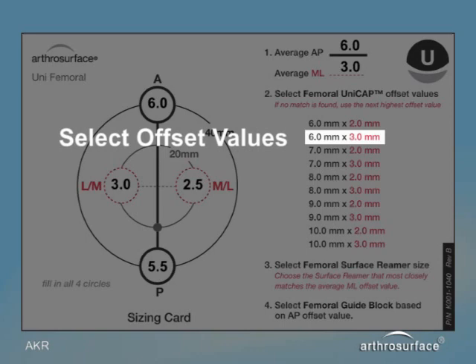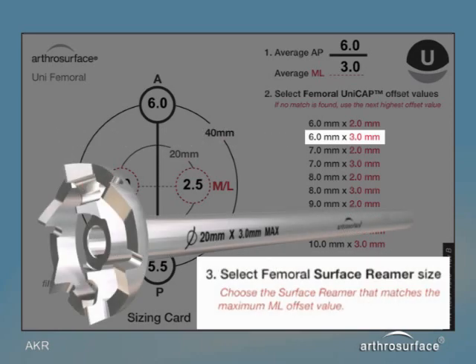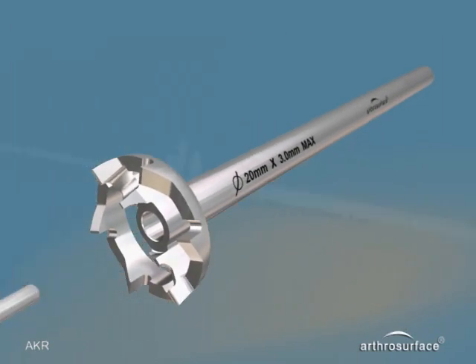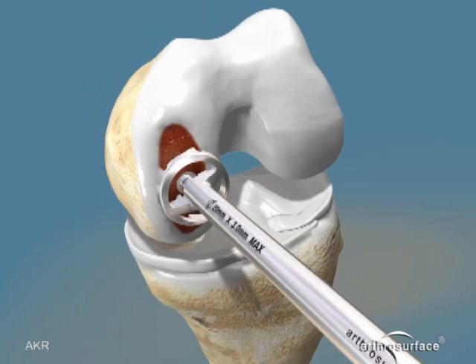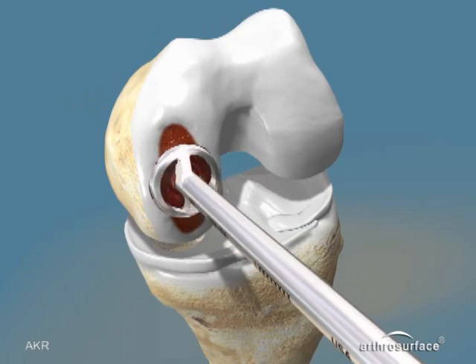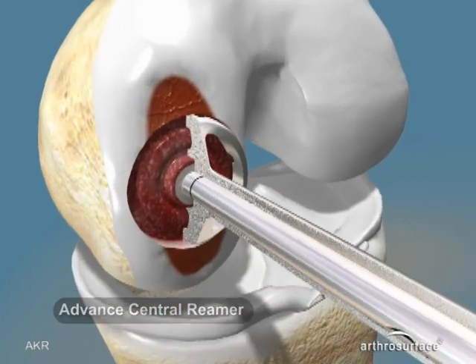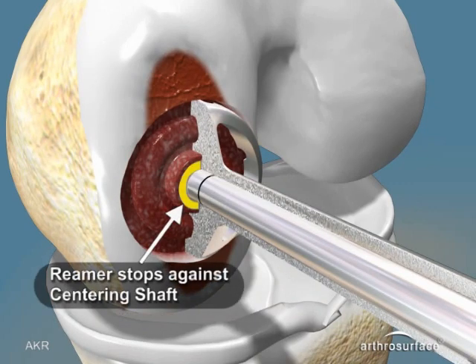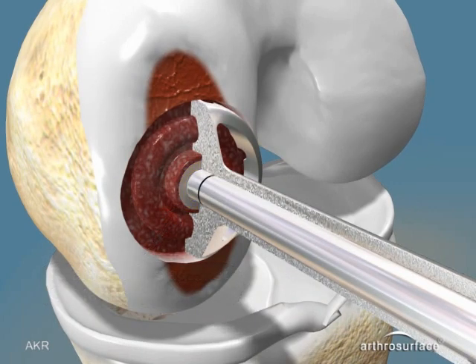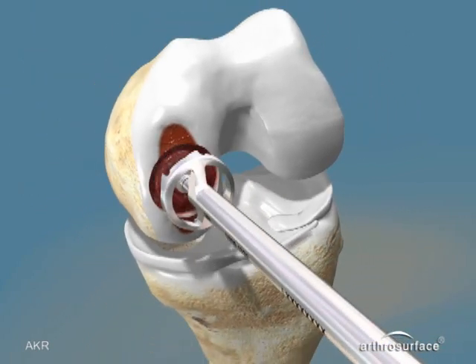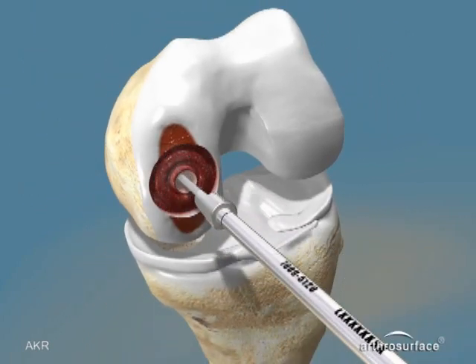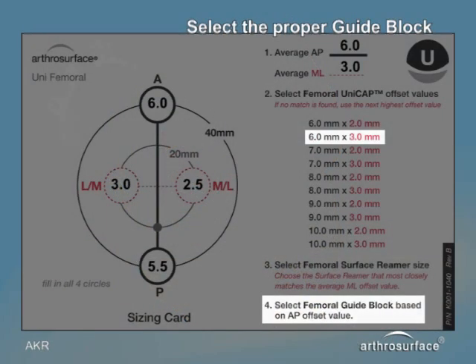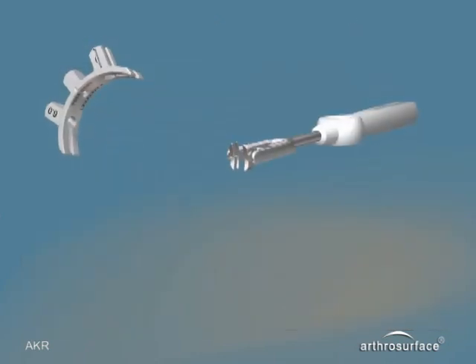The femoral surface reamer is selected based on the medial lateral value, in this case a 3.0 millimeter reamer. Ream over the centering shaft until the reamer bottoms out or stops on the centering shaft. Remove the centering shaft. Select the proper guide block based on the mapping point selected from the anterior-posterior curvature, in this case a 6.0 millimeter guide block.